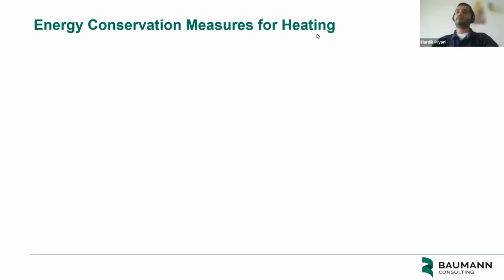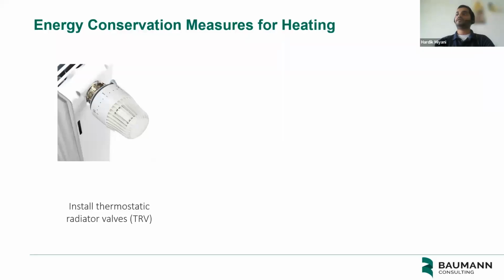These are a few major energy conservation measures that we are seeing in the DC market for heating. One of them is installing thermostatic radiator valves. Majority of the old steam boilers just have a low and high temperature set point, and we have often seen that they just leave it at that. By installing thermostatic radiator valves, it can help you control the temperature in the room by changing the flow of hot water or steam to the radiator.